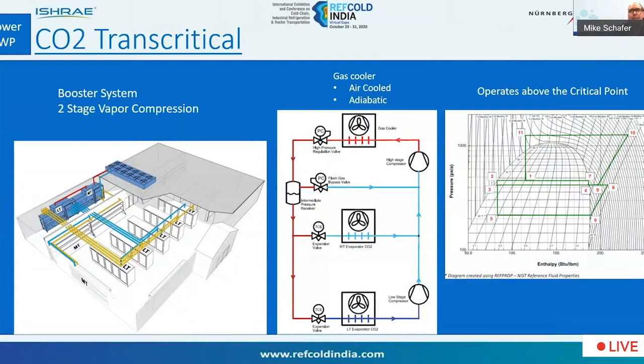So this system has 2 stages. If the store would have low temp cases, the low temp would discharge into the suction of the high stage. Once again, the system would employ a gas cooler that would either be air cooled or adiabatic, as opposed to a conventional condenser. During the subcritical performance, it would act as a condenser, but transcritically, it's a gas cooler.